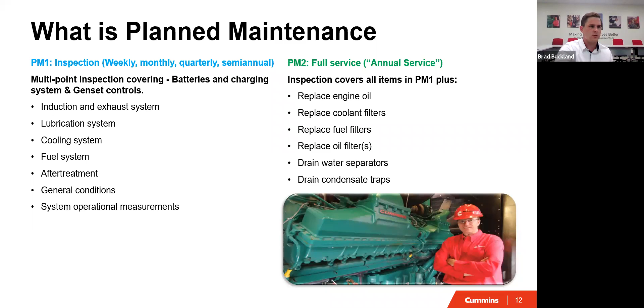Of those additional services, the bigger ones are air filter, belts, and hose replacements. That's about every 3 to 5 years as a standard in the industry, since those parts wear out over time. But if you're checking your generator and there's a hose leak or a small crack, we'll note that and make sure next time we come out we have that part ready to change out, so you're not paying someone else to come out in an emergency when it springs a leak, loses fluid, and leaves you with no reliance on the generator.